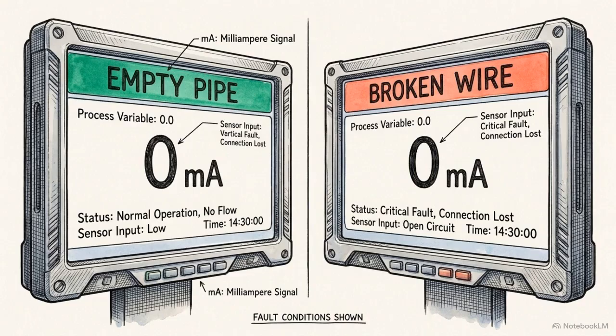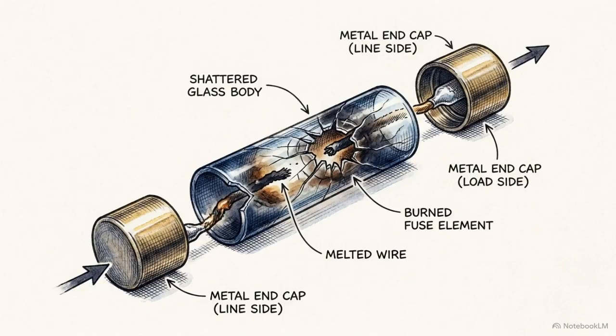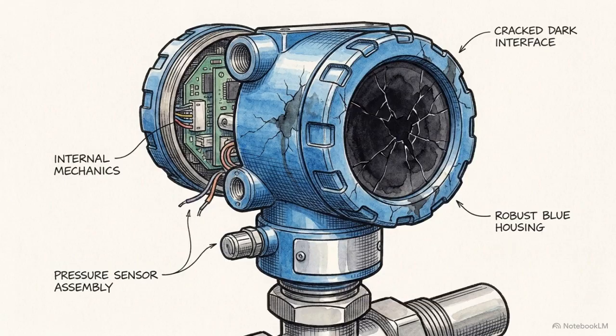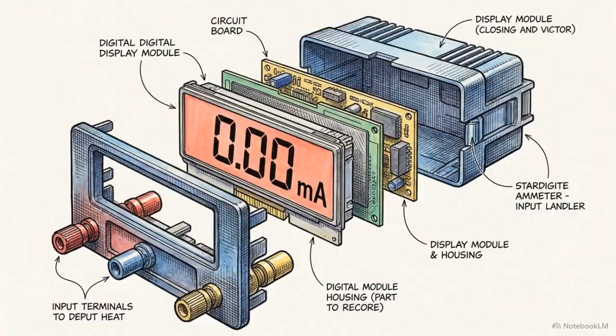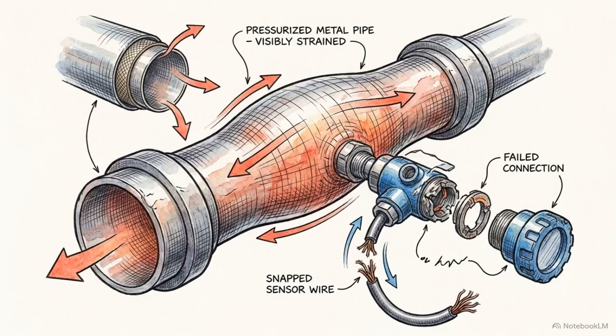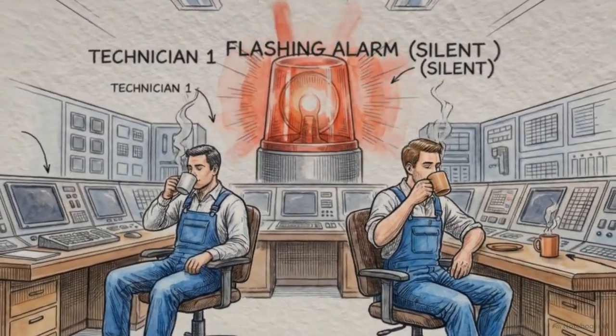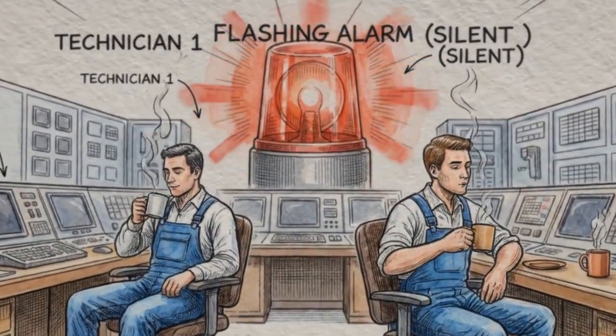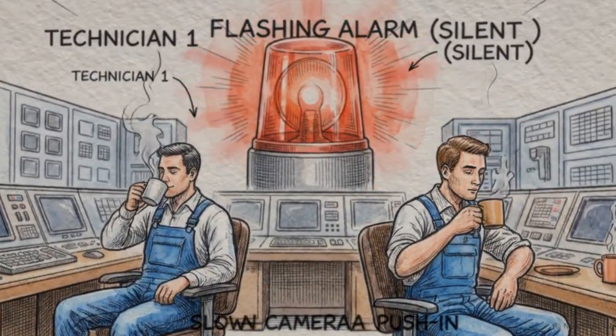But if 0 milliamps means 0 pressure, how does the control system tell the difference between a true 0 reading and a hardware failure? A severed cable, a blown fuse, or a completely dead transmitter all cause the current to drop to 0. In a high-pressure system, a severed wire during a peak event would falsely tell the controller the pressure is safely at 0, leaving operators blind to a mounting disaster.